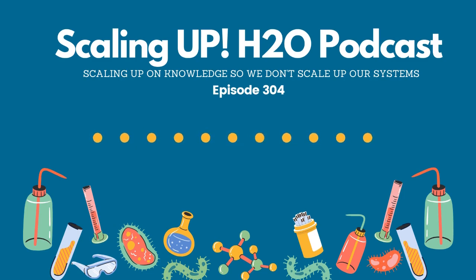So once all that is done in the lab, the person that sent it in will receive a report, and now you've got to take that to the customer and explain to them what you now know about corrosion coupons. Now, the first thing that people want to assume is that whatever corrosion has taken place on that corrosion coupon is uniform through the entire system. And folks, what I said at the top of the show, that is not true. The corrosion you are measuring is the corrosion on that coupon. So that's why you want to try to mimic that G4 standard as much as you possibly can. And the easiest way to do that is to buy a pre-manufactured corrosion coupon holder and use it and install it properly. Just buying that and utilizing that properly alone will eliminate 5 variables that could play havoc with your corrosion coupons.